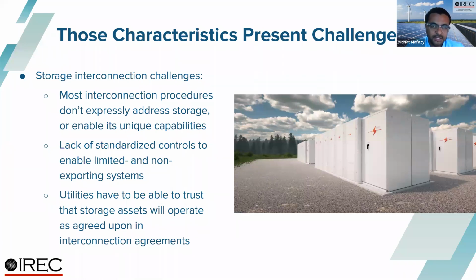Another key challenge is the lack of standardized controls enabling limited and non-exporting systems in interconnection procedures. Standardized controls, such as certified power control systems (PCS) or utility-grade relays, provide a means to streamline applications. If controls aren't standardized, each application continues to face customized review, and reviews will assume storage can export full capacity all the time.